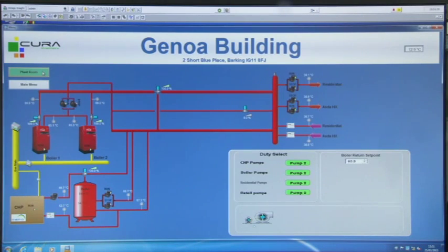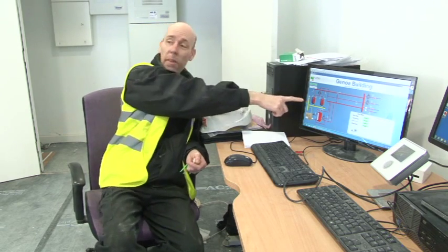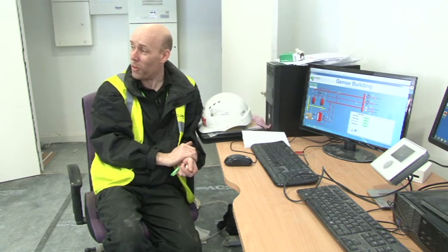So once logged on for the plant room, it will then display the equipment in the same pipe layout as in the plant room. So we have two pictures of Hoval boilers, so at least the picture of the plant shows the plant you've got on the site. So when you say to somebody, my boiler's not working, and they go, what's the boiler? It's one of them, and it matches the picture of the plant that's in the plant room. So at least everybody knows that they're talking about the same bit of kit.